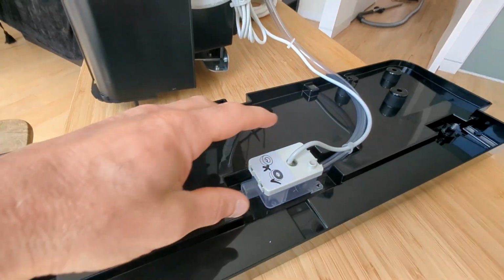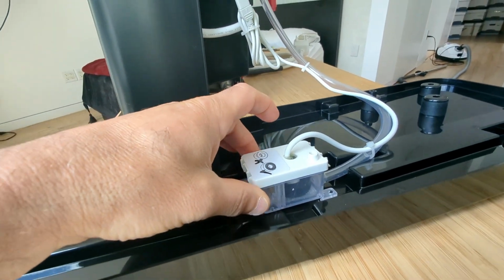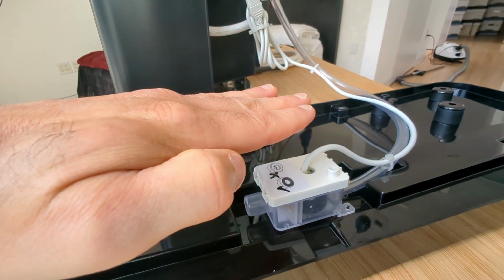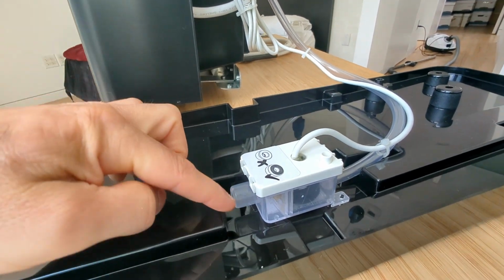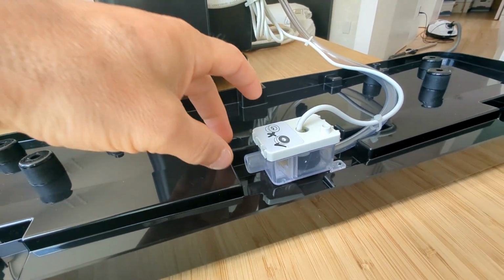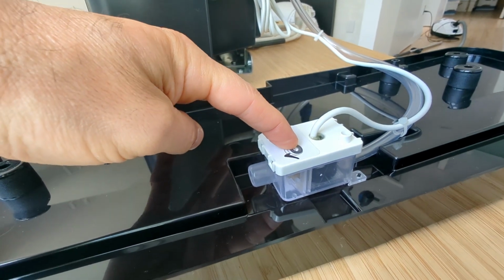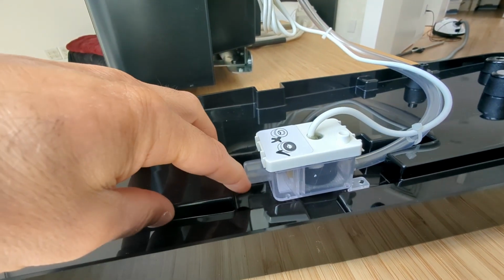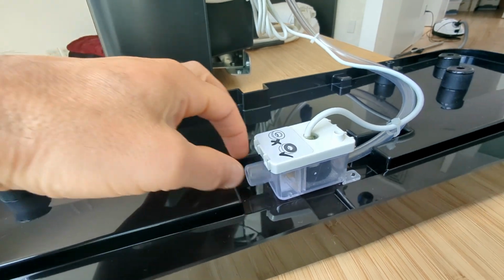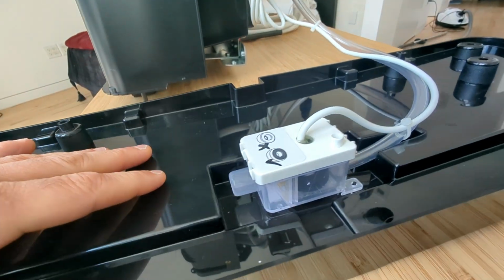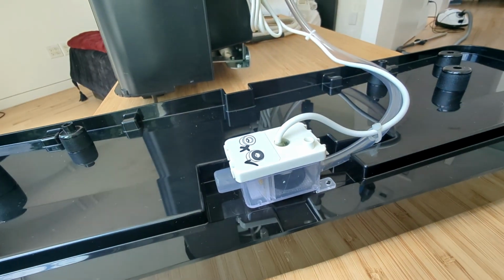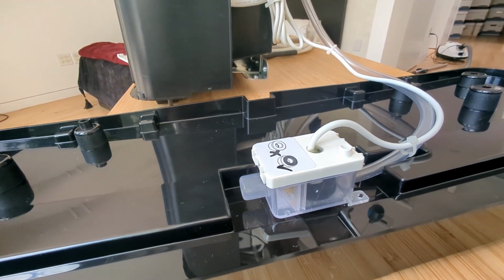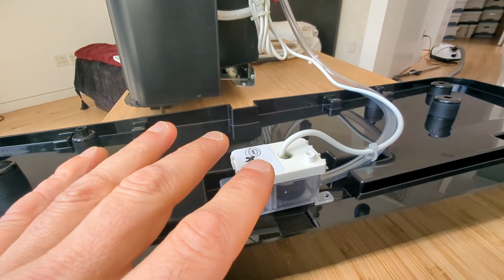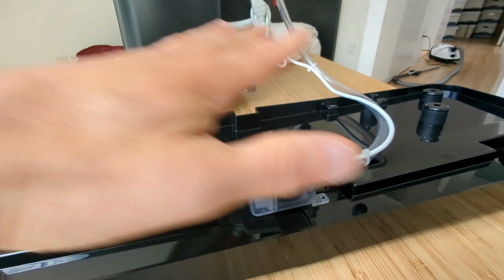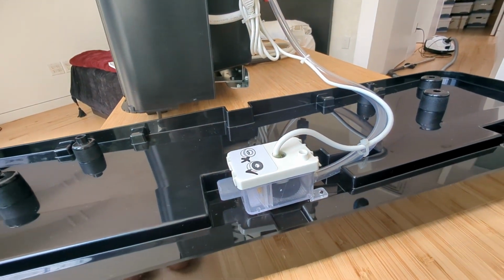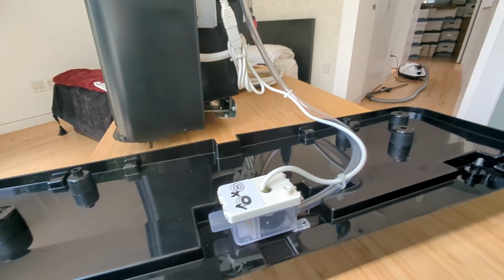A bit of a concern here. This is really designed for use in a mini split where it would be sitting underneath the condensate collection tray and there would be a hose going in here. But here it's just mounted in the bottom of the tray. So that means that there's this gap between the bottom of the port and the bottom of the tray where there's always going to be about a half inch of standing water in the bottom of this tray. Anytime that you have still standing water exposed to air, you risk growing that slime, and that slime just causes so many problems everywhere in the whole system. It can cause things to get jammed and stuck and clogged.